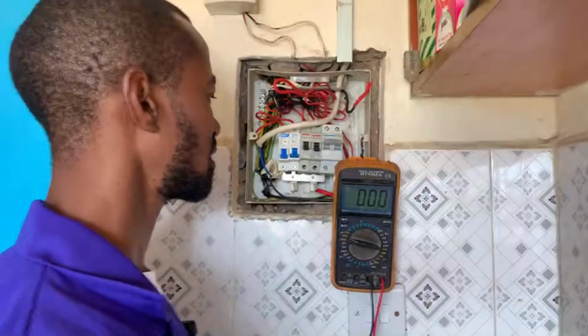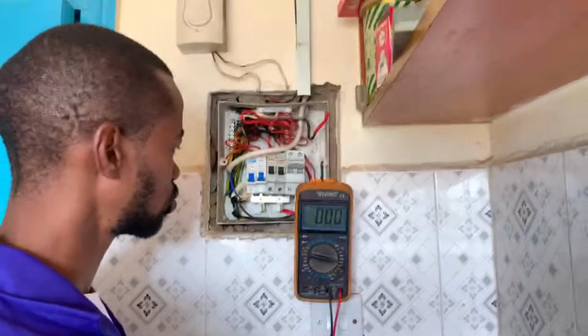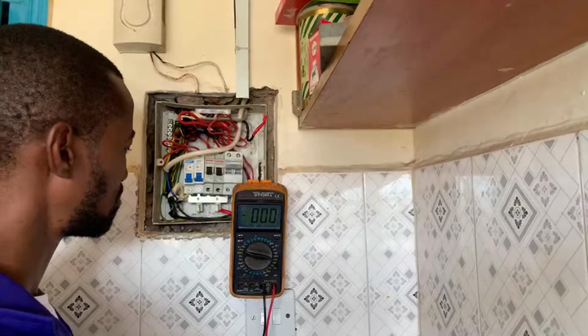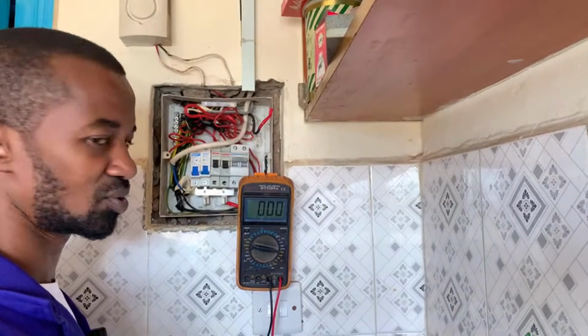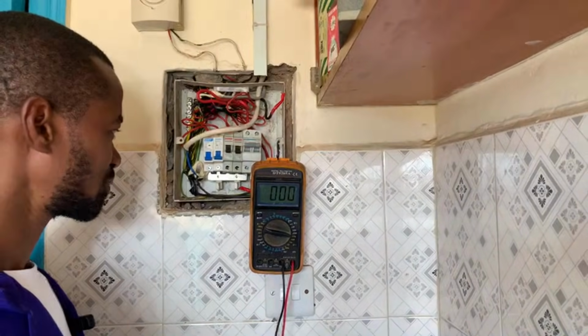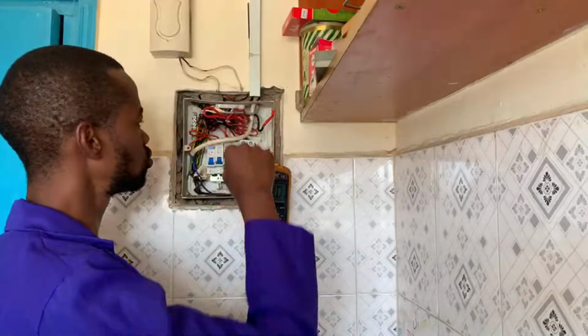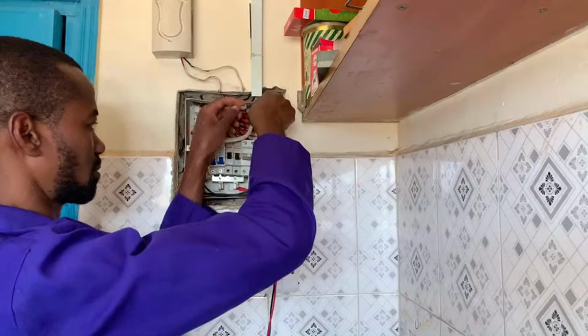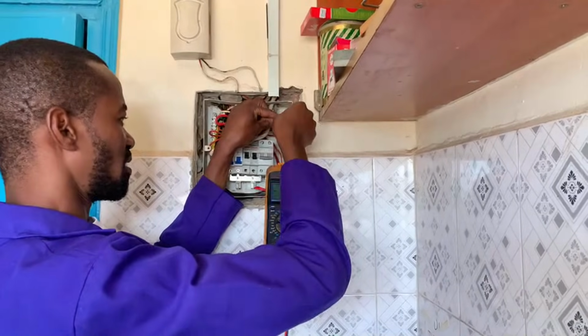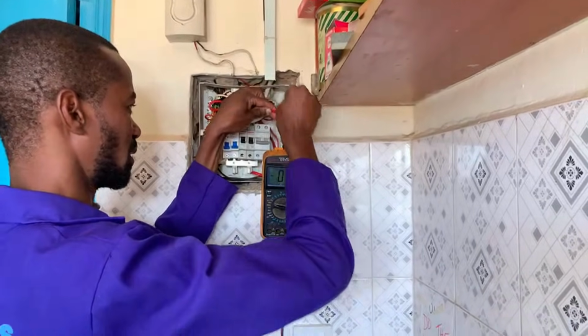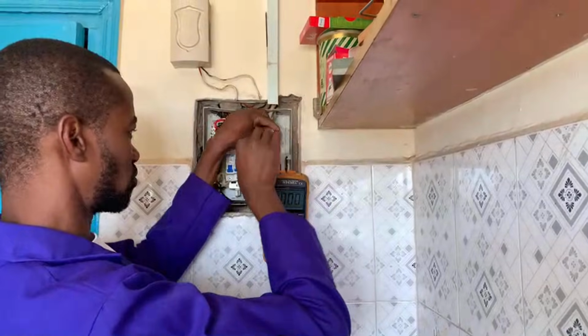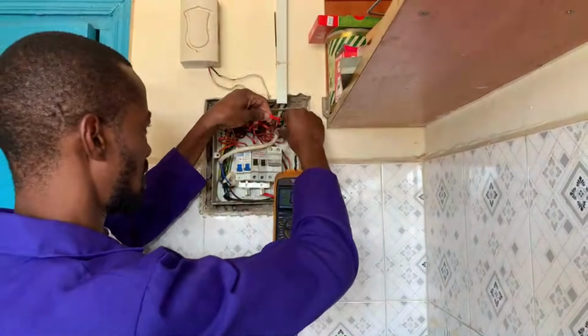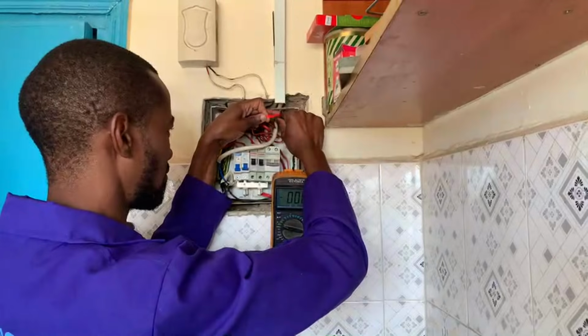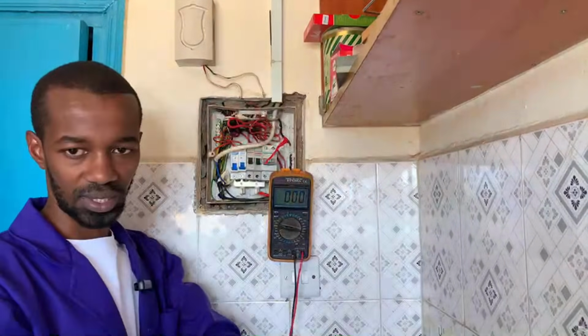Now, using our probes and considering that it is on, we want to make sure that we test the voltage. But remember, we had isolated the neutral. So the next procedure is to simply turn it off and then connect the neutral back. I know I've gone the other route, but I just remembered that we needed to test for that voltage, and we cannot test for the voltage if we don't have the neutral, isn't it, Margaret?